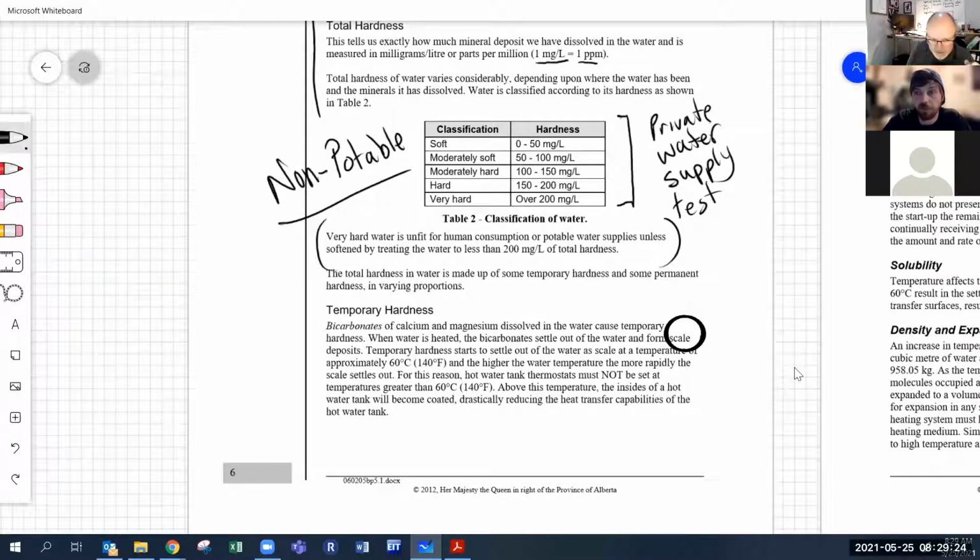Yeah, we were just doing a 2-inch copper line clean, an exchange from a hot water tank, and we cut open the line, and probably 65% of the pipe was layered in little white crystals, layer by layer by layer.